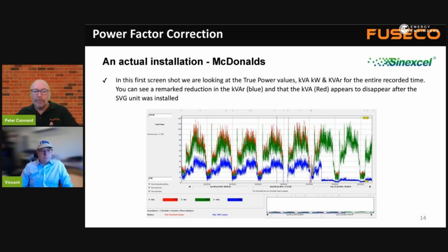So you have no power factor—well, very little power factor. That's the goal. You see the remaining kilowatt consumption in green, and the red disappear. But the red isn't actually disappearing; it's tucked in behind the green. The arrows on that triangle we saw before are the same length now, so the kVA is the same length as the kilowatt. You'll see a tiny bit of red when loads are very, very low—it's not a perfect system. So there's virtually no power factor issue, virtually no kVAR, virtually no kVA, but it's not perfect at really partial loadings. Still, it's pretty good.